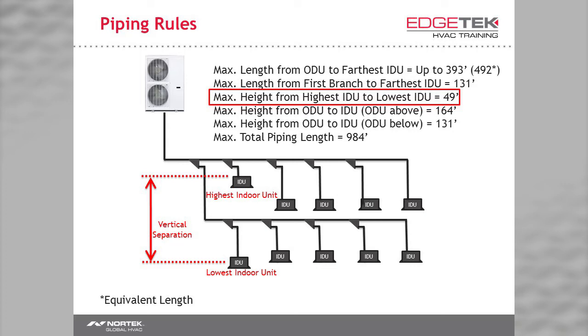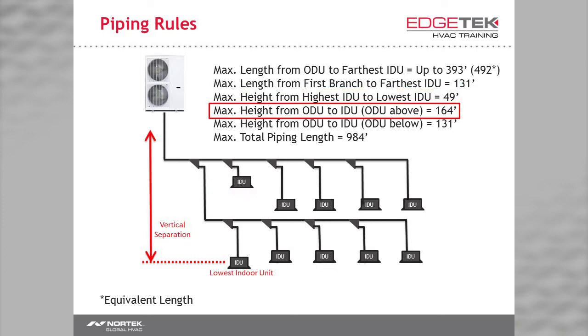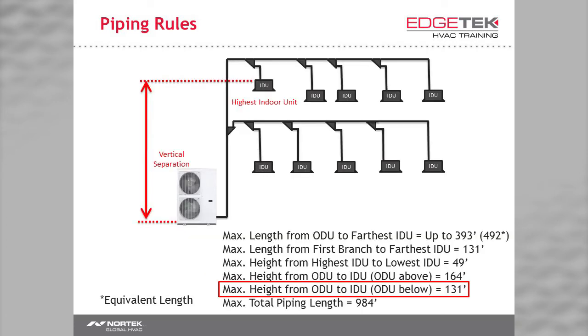Although we've seen this beast push refrigerant 393 feet and back, pumping up and down is significantly more difficult. So the max height difference between indoor units is 49 feet, or like only 3 or 4 stories. If you were to install this outdoor unit above the indoor units, like on a roof, the outdoor unit can pump all the way down to 164 feet to the lowest indoor unit. In the opposite configuration, like where the outdoor unit is pumping up, your highest indoor unit must be 131 feet or less from your outdoor unit.